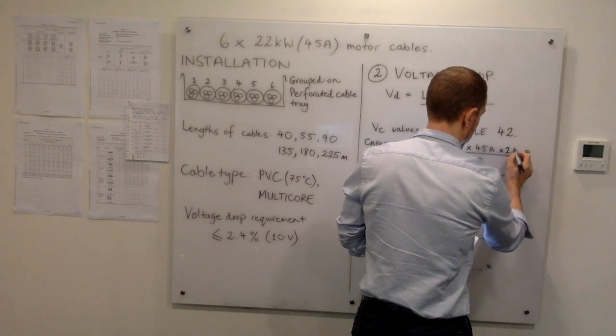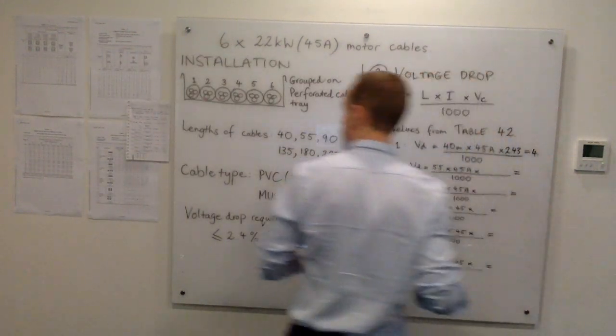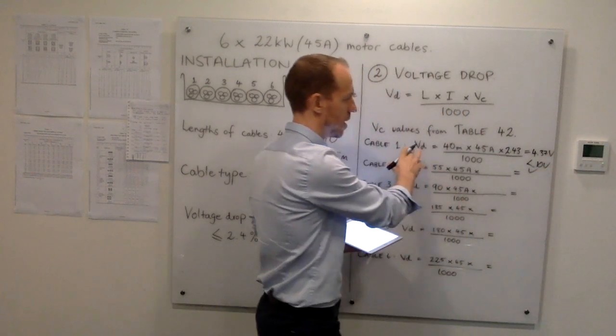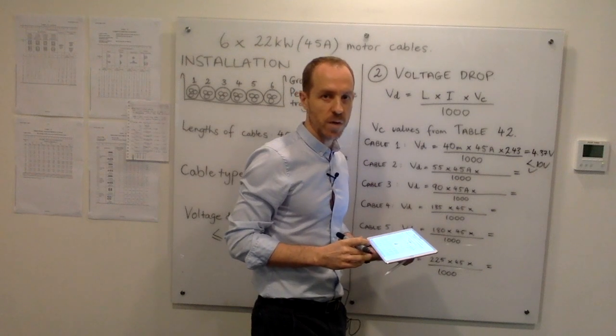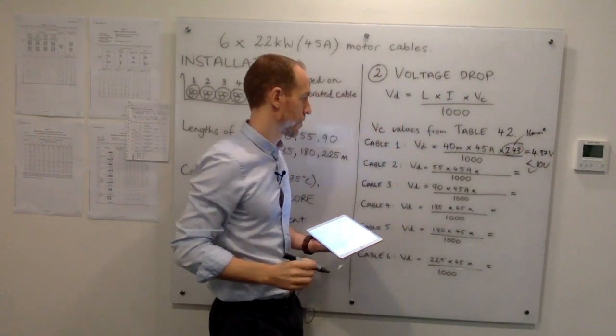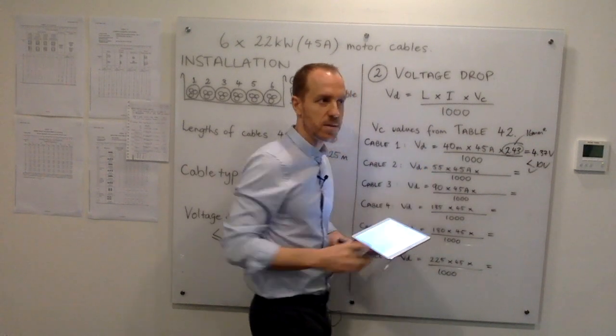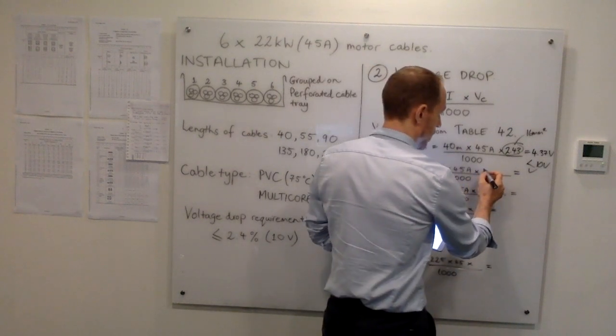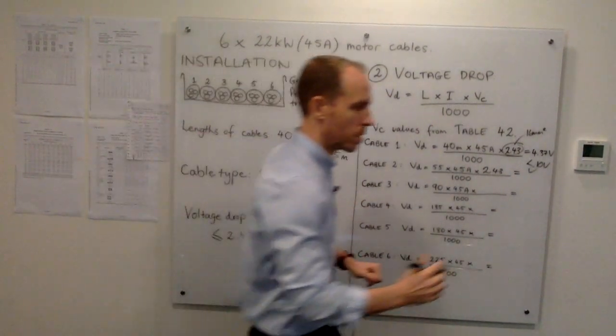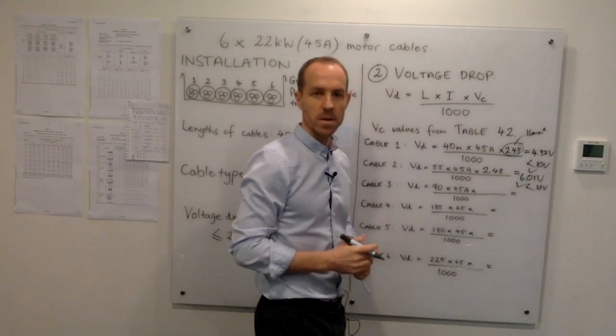For cable 1 at 40 metres: 40 times 45 times 2.43 divided by 1,000 gives a voltage drop of 4.37 volts, which is less than 10 volts. So a 16mm² cable is fine for cable 1. Moving on to cable 2 at 55 metres — using a VC value of 2.43, the voltage drop is 6.01 volts, again less than 10 volts. So 16mm² is fine for cable 2.